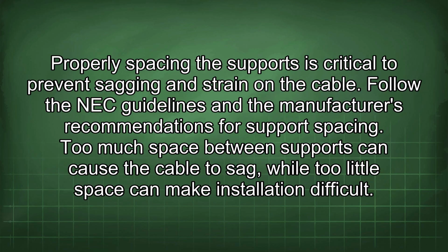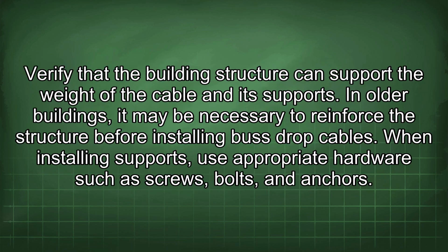Properly spacing the supports is critical to prevent sagging and strain on the cable. Follow the NEC guidelines and the manufacturer's recommendations for support spacing. Too much space between supports can cause the cable to sag, while too little space can make installation difficult. Verify that the building structure can support the weight of the cable and its supports. In older buildings, it may be necessary to reinforce the structure before installing bus drop cables.